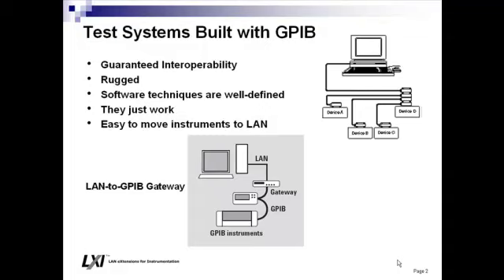With a LAN-to-GPIB gateway, you take that same subsystem of instruments on GPIB, connect them to that gateway, and the gateway itself is connected to a LAN. This is a very common configuration where you have a single LAN cable coming from your PC to a rack of instrumentation. But let's talk more about actually getting to LAN-based instrumentation.